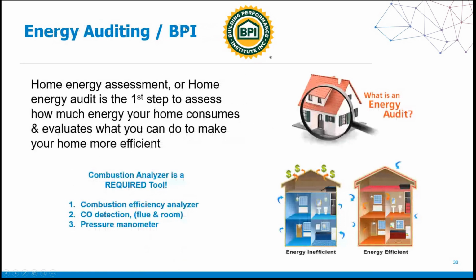Energy auditing, BPI, like I just touched upon. Again, home energy assessments want you to do the combustion test. They want to make sure that we're not sealing up spaces so tight that we're producing excessive levels of carbon dioxide and producing high levels of moisture inside of a space because we're sealing them up too tight. And also, we want to make sure that we're having proper levels of CO in the different living quadrants in the house, or building, and also in the actual appliance itself. And again, this information needs to be uploaded for you to qualify for your payment, and it's part of your general operational protocol as a BPI contractor.